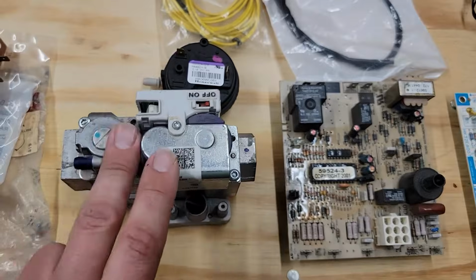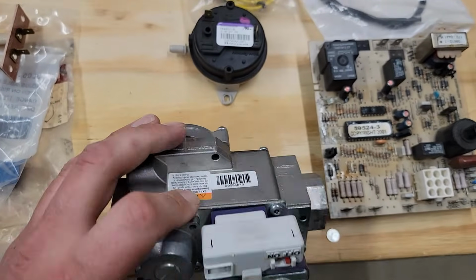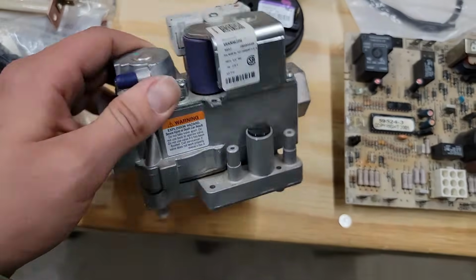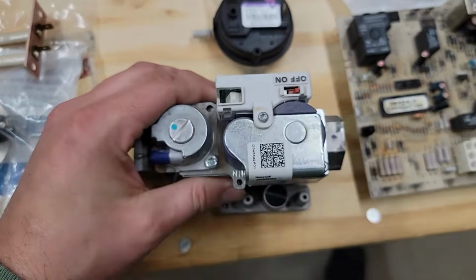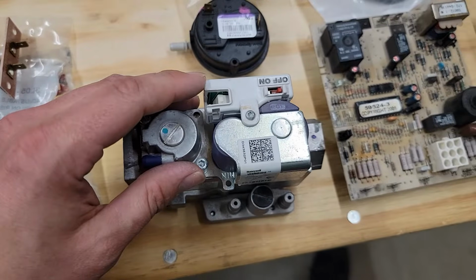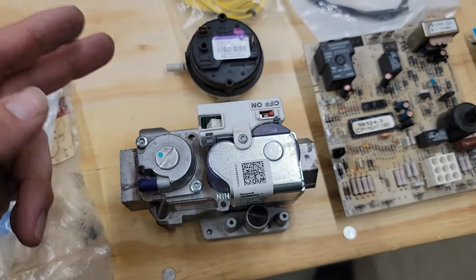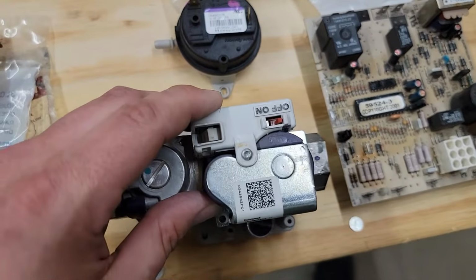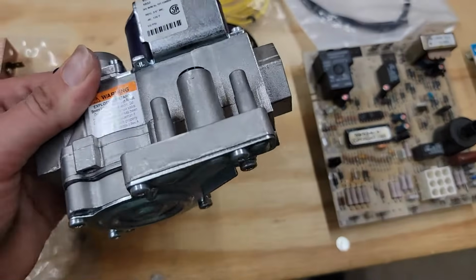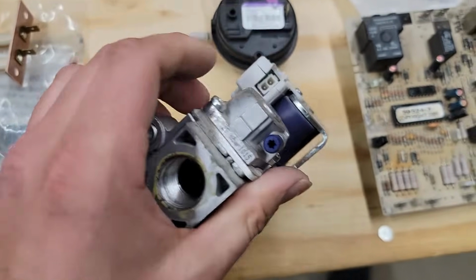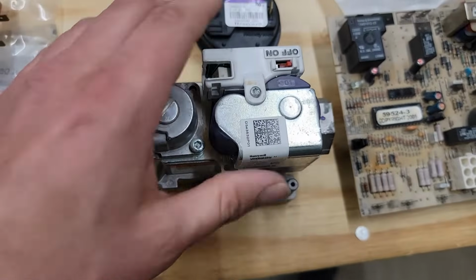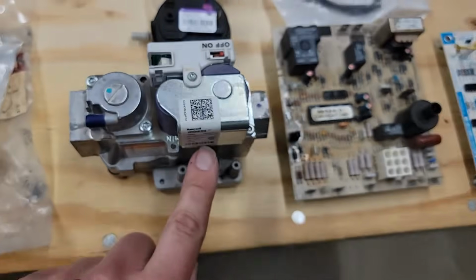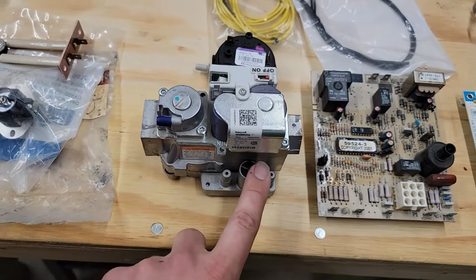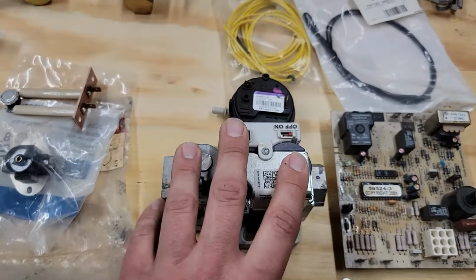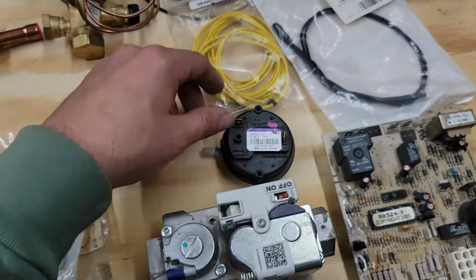All right, gas valve. Gas valve opens and closes, sends gas to the manifold and the orifices, and then through these burners here. And this right here has a 24-volt valve. So anytime you energize, you've got 2 wires, common, and then that call for the gas valve, it's going to open. It opens the diaphragm and sends gas in through the valve and then out the other side. Usually you can measure the gas because there is an inlet and an outlet screw, and usually it says in and out, and you're able to use a manometer. If you don't know how, check out my playlist. I got a video on that.